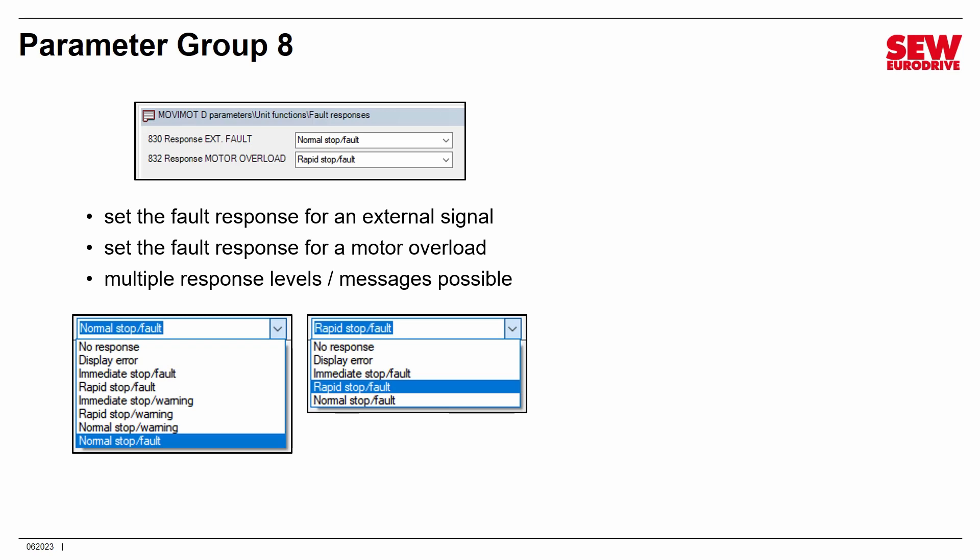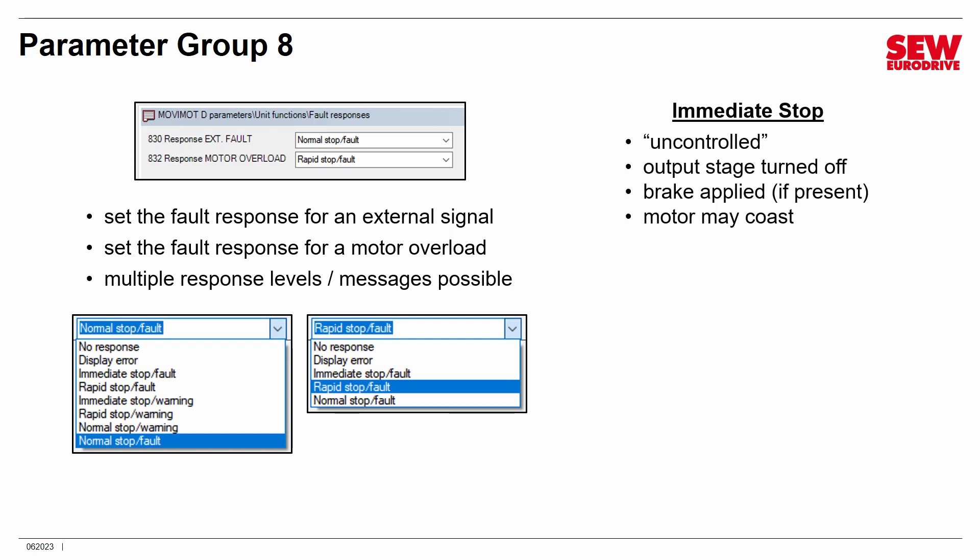You may wonder about the difference between the types of stops. Movimot can stop itself in three ways. An immediate stop is an uncontrolled stop — the Movimot simply switches off the output transistors and attempts to apply the brake if present. If there's no brake, the motor may coast a long time depending on load momentum. A rapid stop is a controlled stop: the Movimot uses the ramp value set in parameter 136 to deliberately slow the motor down, then turns off the output transistors and applies the brake. This gives a predictable stop time.